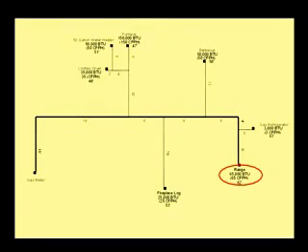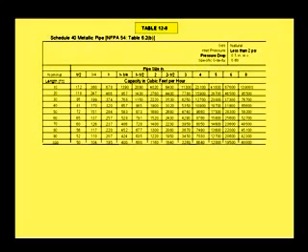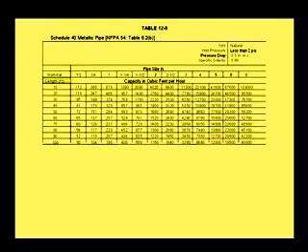Beginning at the most remote appliance and working back to the meter, we have the range with a demand of 65 cubic feet per hour. Refer to table 12-8. Under length in the left column, locate the row that will accommodate 62 feet, which is the 70-foot row. Once you locate the appropriate row, never change from this row when calculating the main supply line. Looking to the right to find the number that will allow 65 cubic feet per hour — 126 — we see that a 3/4-inch pipe will accommodate the 65 cubic feet per hour demand for the range.